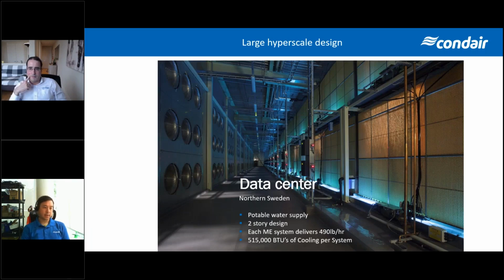So I think the next slide shows that fairly well in terms of the setup. This was a fairly large plenum design, so not dedicated air handlers like you would traditionally see. But in this case, air is moving from the right to the left. We're drawing that mixed air through the evap cooler, through the fan section, and that's being supplied directly into the white space. So just to give you an idea of the scalability of these types of applications and systems.